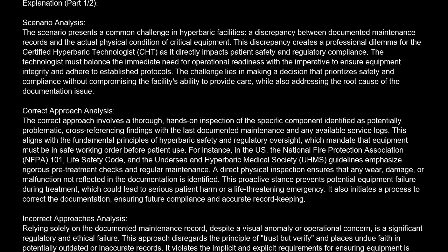Correct approach analysis. The correct approach involves a thorough, hands-on inspection of the specific component identified as potentially problematic, cross-referencing findings with the last documented maintenance and any available service logs. This aligns with the fundamental principles of hyperbaric safety and regulatory oversight, which mandate that equipment must be in safe working order before patient use. For instance, in the U.S., the National Fire Protection Association, NFPA 101, Life Safety Code, and the Undersea and Hyperbaric Medical Society, UHMS, guidelines emphasize rigorous pretreatment checks and regular maintenance.